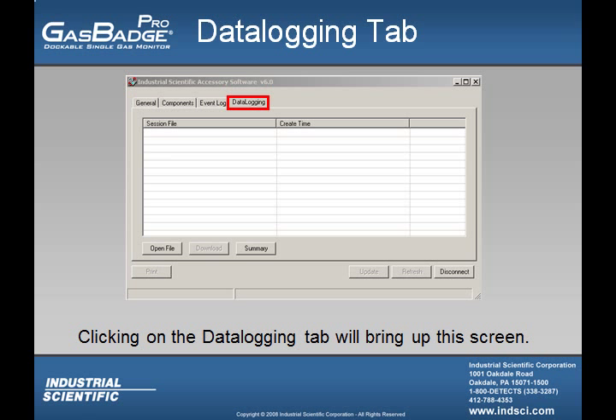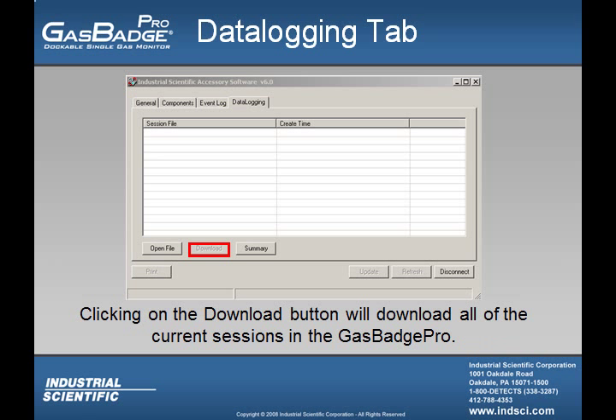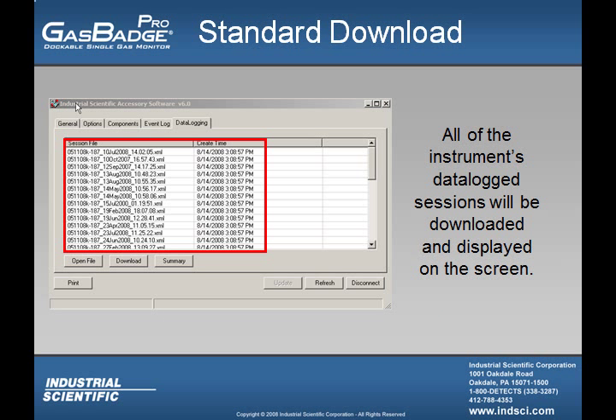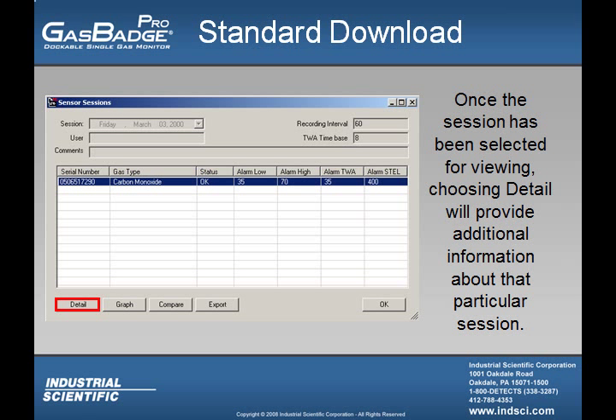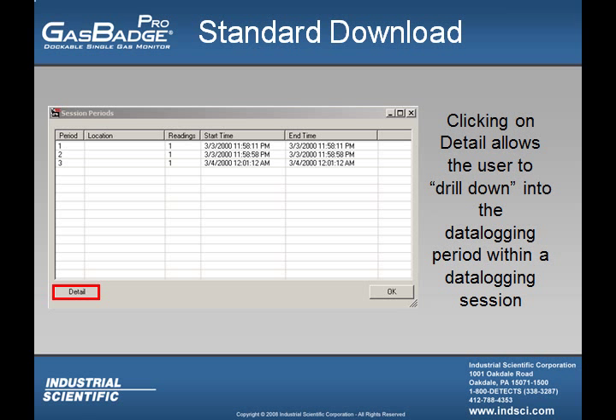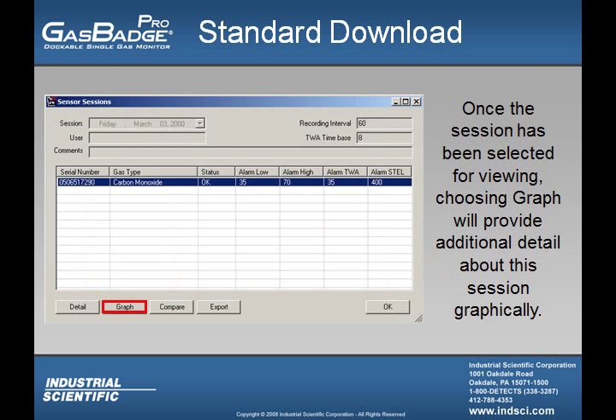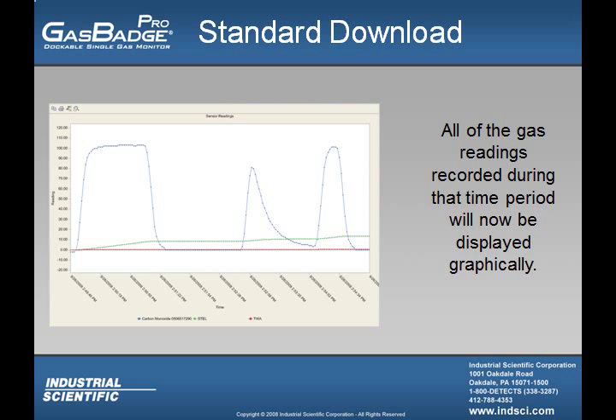If the user clicks on the Data Logging tab, they will see the data logging screen. Clicking the Download button, the Datalink software will download all of the current sessions within the Gas Badge Pro, and all instrument sessions will be displayed on the screen. If the user wants to open one of the sessions, they must highlight the session and click on the Open File tab. Once that session is open, they can click on the Detail tab for additional information, and drill down into the specific data logging period they want to view. The user can then click on the Graph tab and the Datalink software will display the session information graphically, showing all readings the instrument saw during the session.